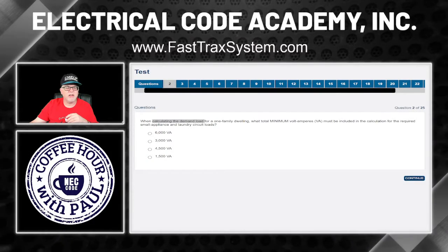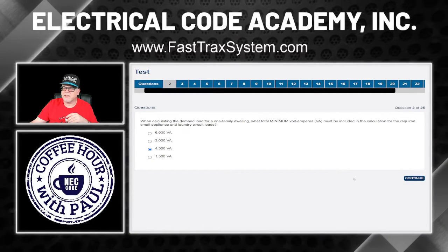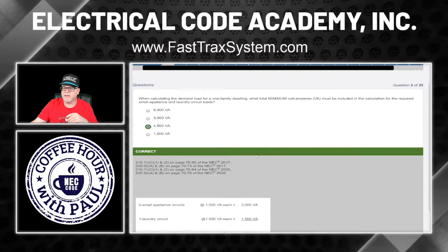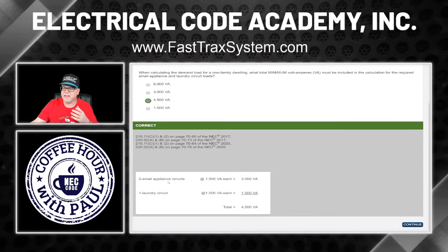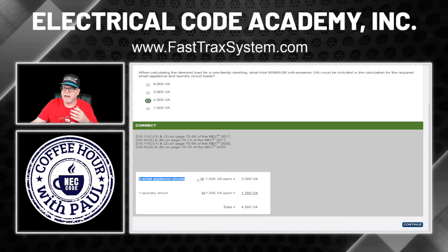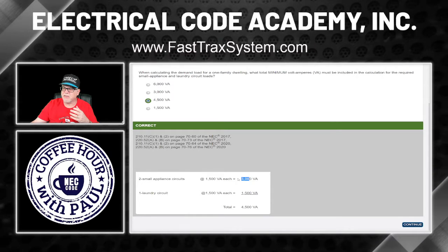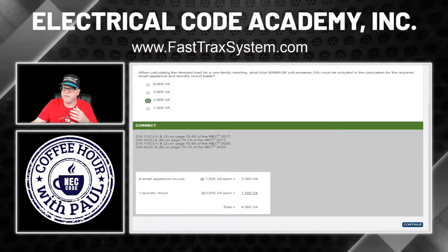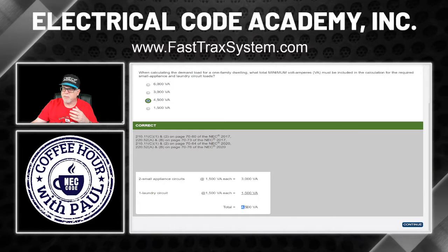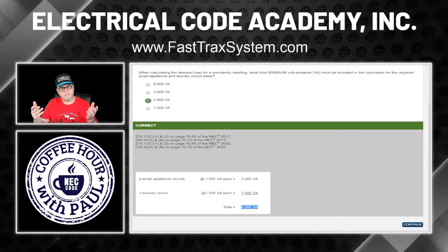Here we're at the question. And let's go on and click that. And there you go. That's correct. And there's the math logic right there. 2 small appliances, 1,500 each. That's 3,000. And then you have the 1 laundry, 1,500. Okay. So 4,500 total. And that was our answer.